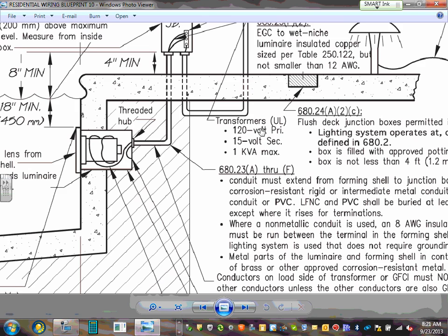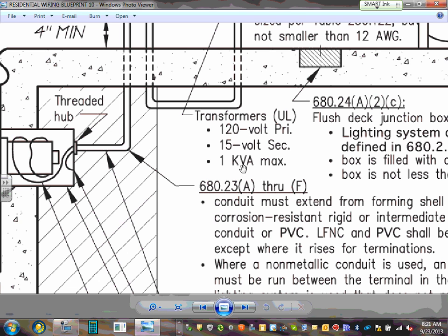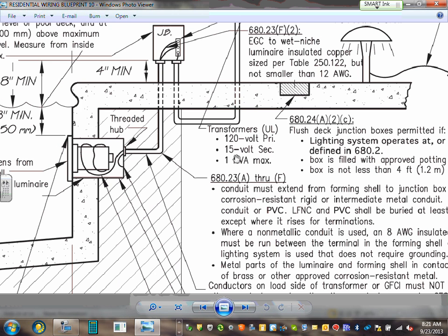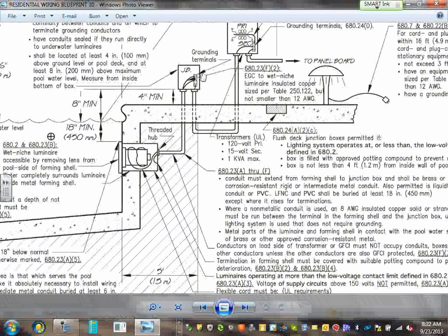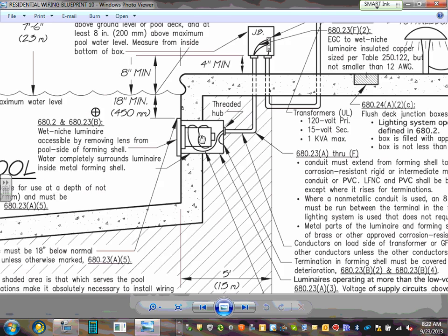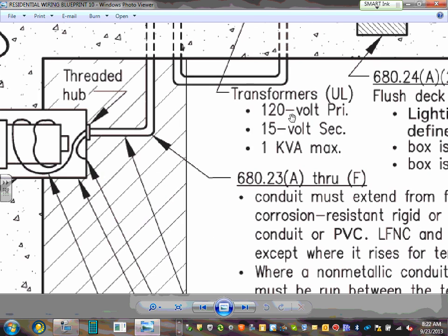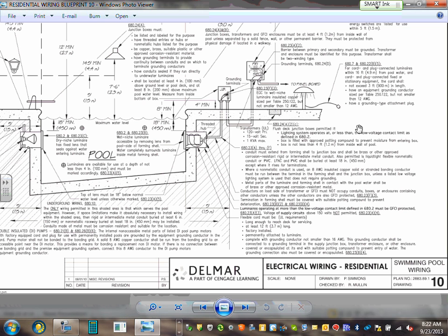Transformer 120. Look at the transformer they use for wet niche, guys. 120 volt primary, 15 volt secondary, 1 kVA isolation transformer. If you want to use these lights for your project, wet niche luminaire fixtures, then be aware that this will have a transformer that's going to be taking the 120 into typically 15 volt or 30 volt or 24 volt, and dumping it across an isolation transformer, an ungrounded system, for safety. So every time you see that wet niche luminaire, remember they're typically running it at a lower voltage, non-lethal, with an isolating transformer. Okay.